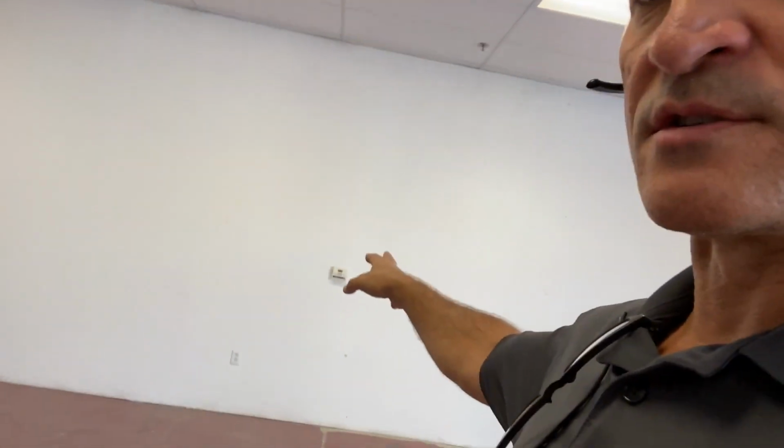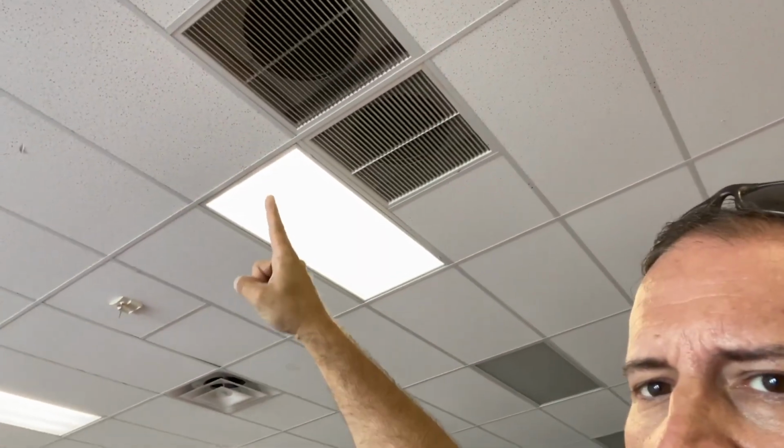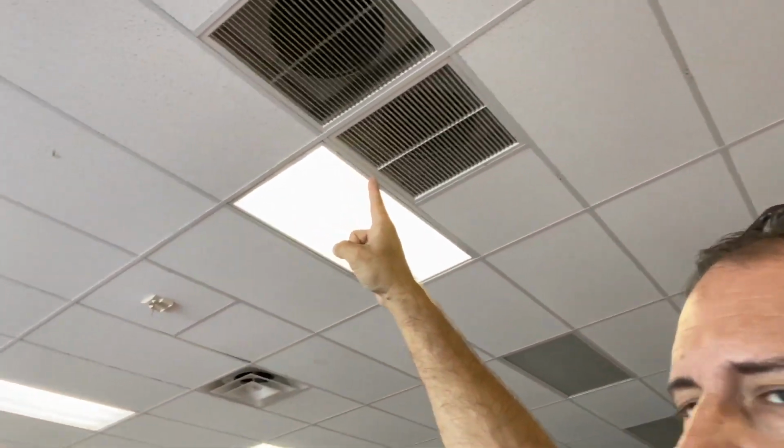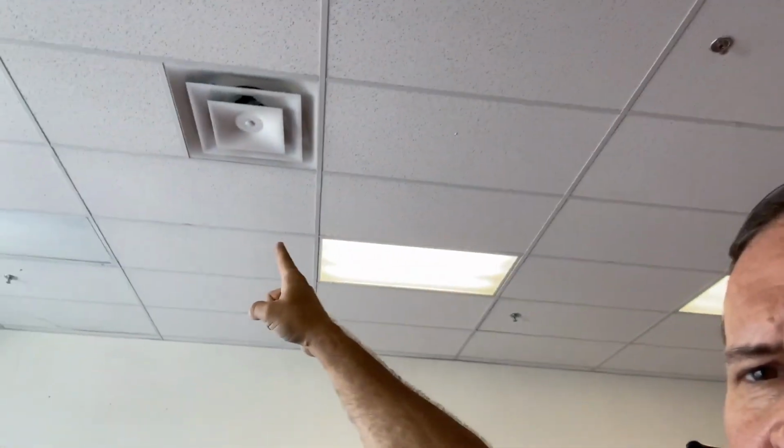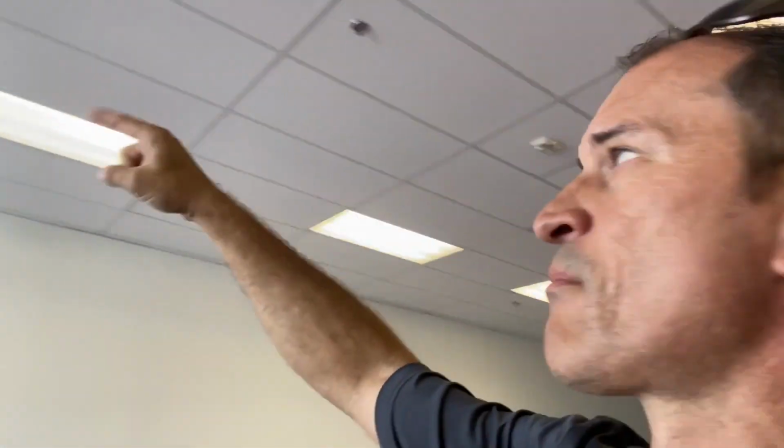Next thing I'm going to look at is the units here. How many AC units are in the space? And my secret to that is really I look for thermostats and I look for return air ducts. I know that before I even climb on the roof, and in some cases I don't need to do that until I need to go look at the specs and look at the sizes. So we have 1 unit here, and these are returns. You see the difference in that grill in comparison to that one?